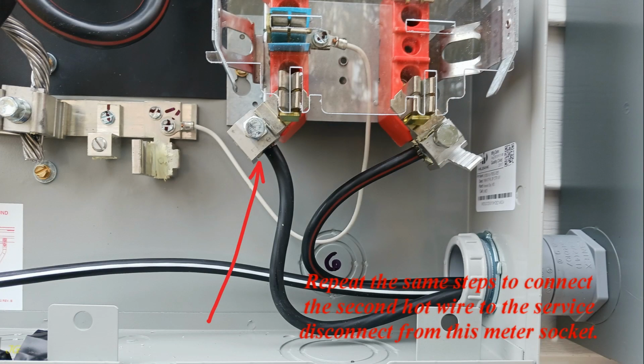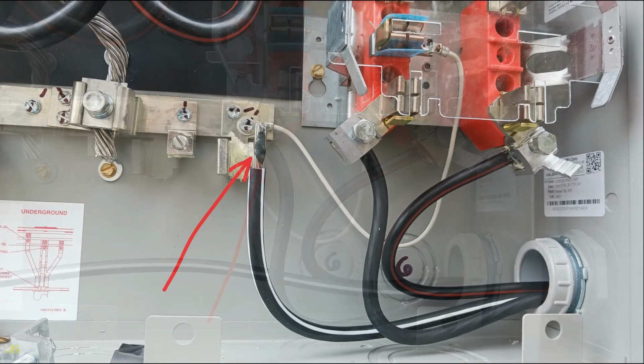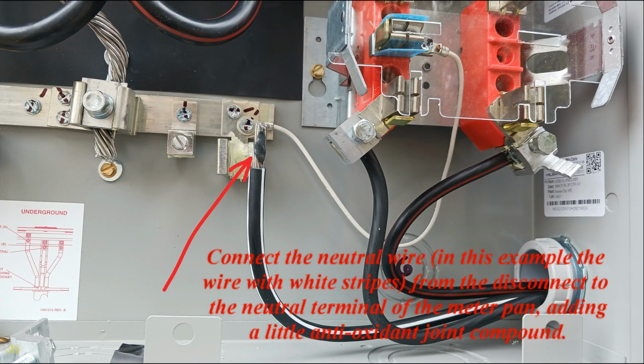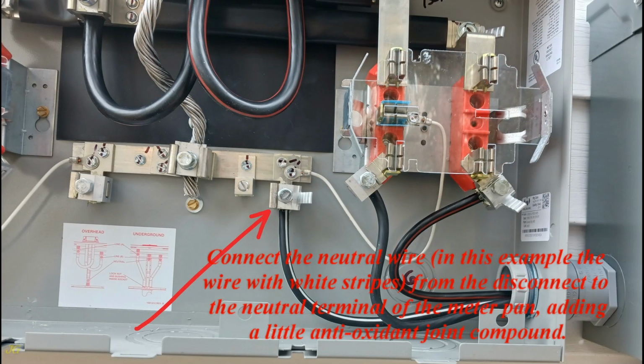Repeat the same steps to connect the second hot wire to the service disconnect from this meter socket. Connect the neutral wire, in this example the wire with white stripes, from the disconnect to the neutral terminal of the meter pan, adding a little antioxidant joint compound.